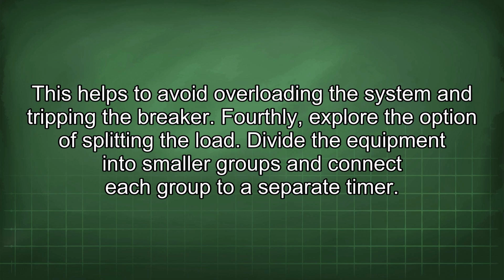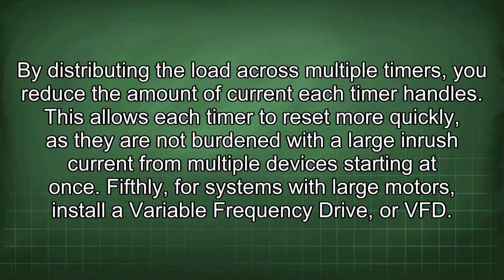Fourthly, explore the option of splitting the load. Divide the equipment into smaller groups and connect each group to a separate timer. By distributing the load across multiple timers, you reduce the amount of current each timer handles. This allows each timer to reset more quickly, as they are not burdened with a large inrush current from multiple devices starting at once. Fifthly, for systems with large motors, install a variable frequency drive, or VFD.